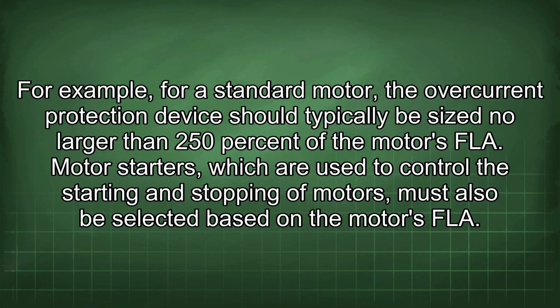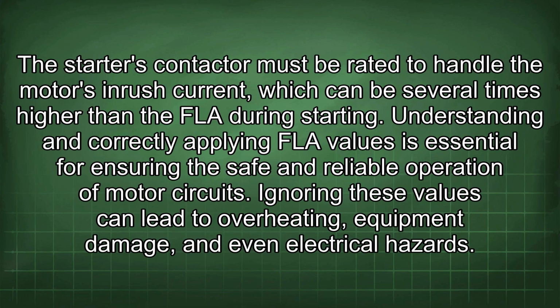Motor starters, which are used to control the starting and stopping of motors, must also be selected based on the motor's FLA. The starter's contactor must be rated to handle the motor's inrush current, which can be several times higher than the FLA during starting.